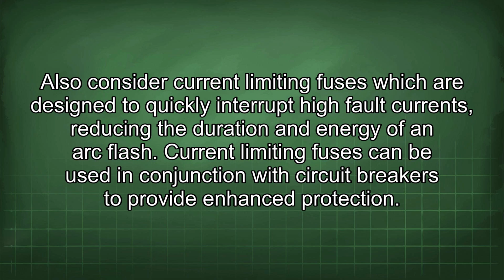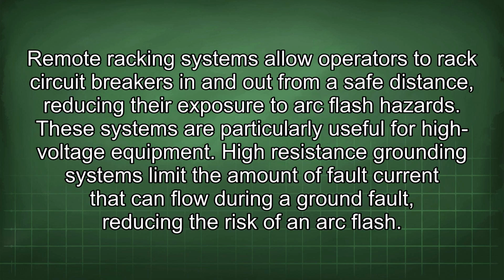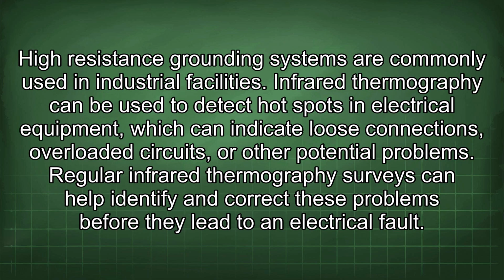Also consider current-limiting fuses, which are designed to quickly interrupt high fault currents, reducing the duration and energy of an arc flash. Current-limiting fuses can be used in conjunction with circuit breakers to provide enhanced protection. Remote racking systems allow operators to rack circuit breakers in and out from a safe distance, reducing their exposure to arc flash hazards. These systems are particularly useful for high-voltage equipment. High-resistance grounding systems limit the amount of fault current that can flow during a ground fault, reducing the risk of an arc flash. High-resistance grounding systems are commonly used in industrial facilities.